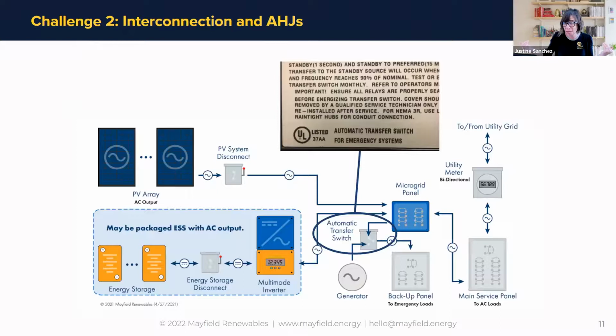We still were able to make our goal, and that goal for this particular project was to run for 2 weeks with 1,000 gallons of diesel fuel, with our 250 kW PV and energy storage system, to run 2 weeks without the utility being present. Even with isolating the generator, we're still supposed to be able to do that at any time of the year, which is nice.